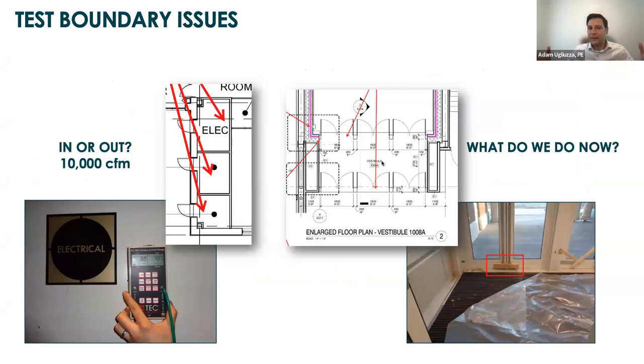I started up the test and it wasn't meeting performance requirements. So I thought, I should go and test and check those rooms. And sure enough, what were supposed to be firewalls that were airtight were not at all. And those rooms were actually being pressurized equally to the rest of the building. And it was a 10,000 CFM swing. So it was very important that I figured that out. And again, back to that test boundary, in this case, there was never a clear definition of where that boundary was. And I was sort of helping them figure that out on the fly.